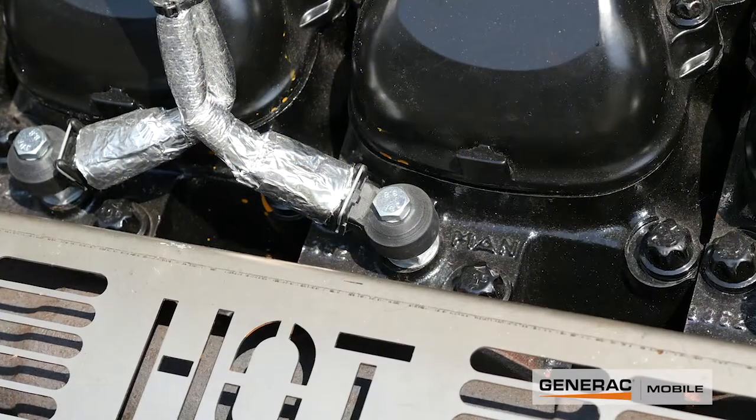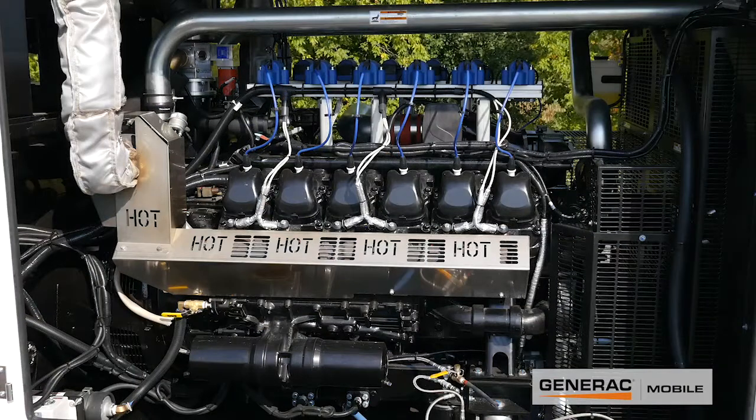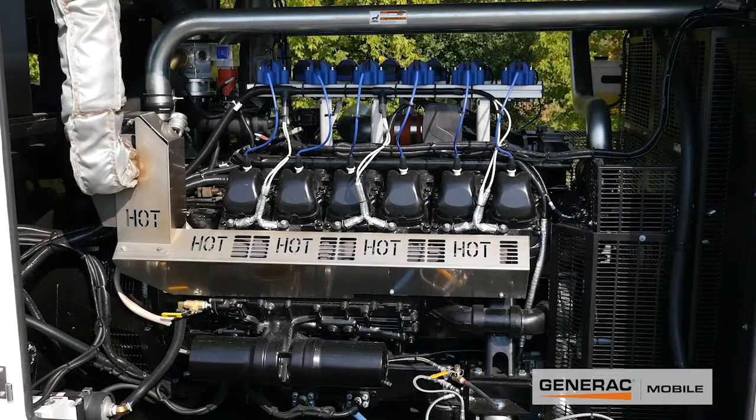On all the cylinders we have individual cylinder knock sensing. If the unit does experience knock, those sensors will pick it up and the MOTORTECH ignition will reduce timing to try to prevent that knock. If that timing reduction isn't able to eliminate the knock, it will put the unit into a warning mode, and if it's bad enough, a shutdown mode, so you don't harm the engine.